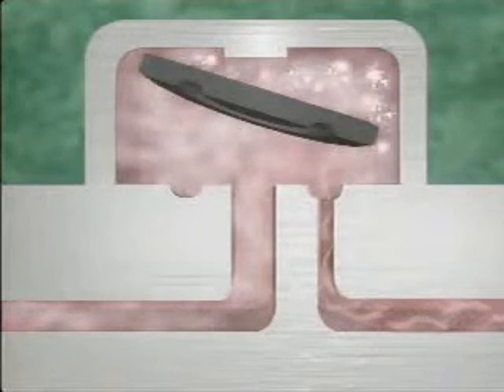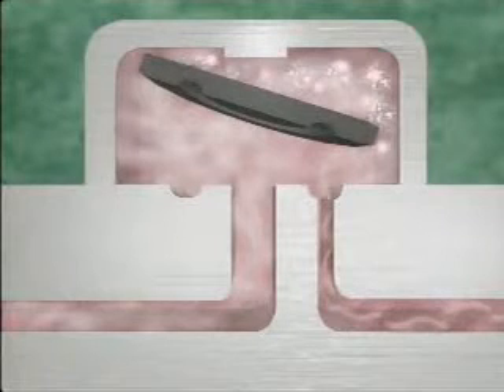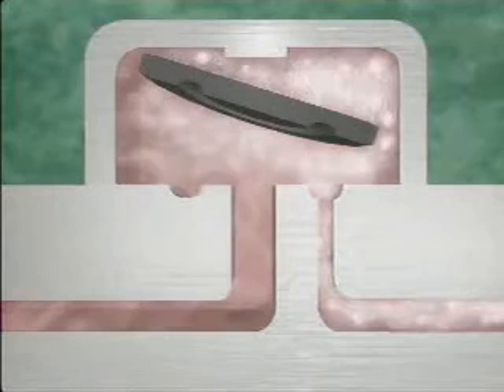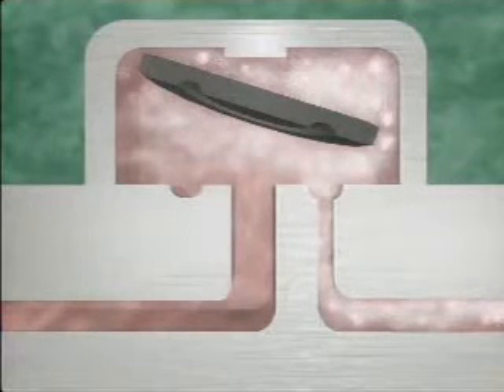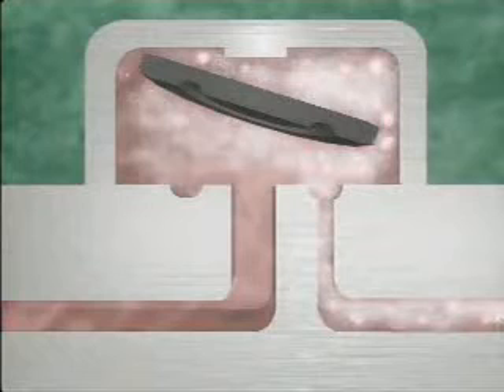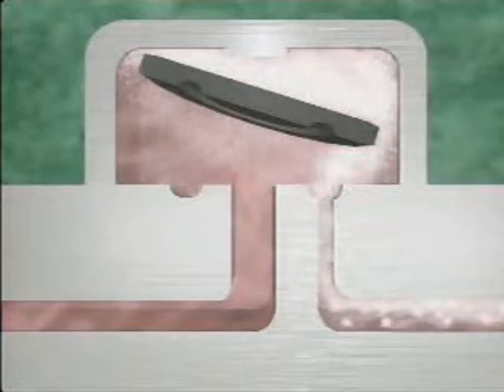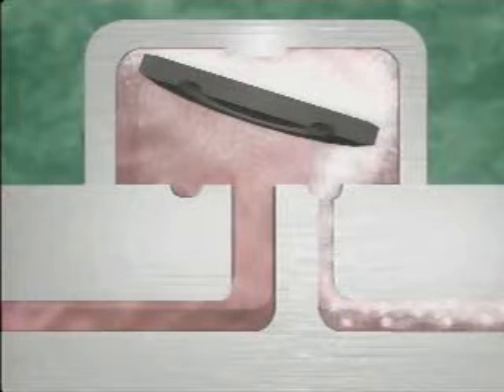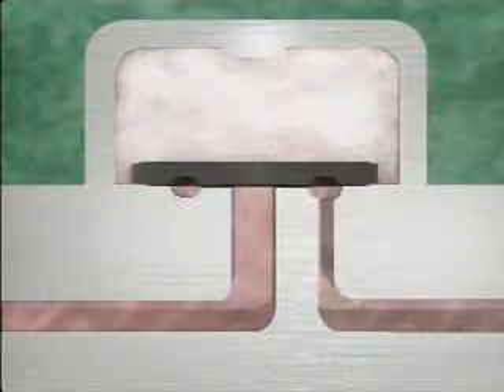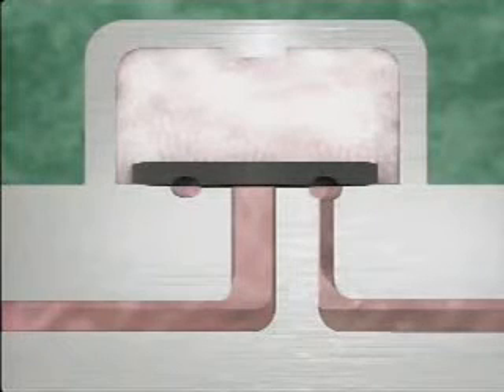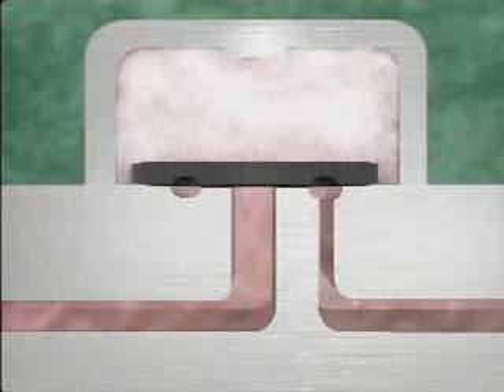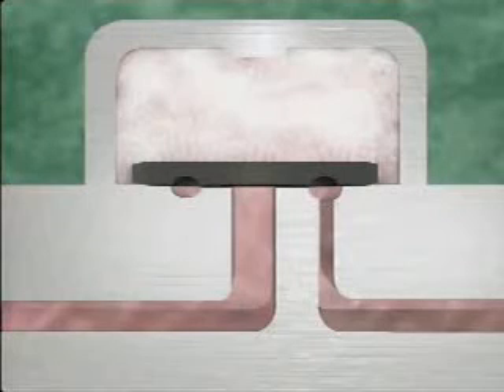This further increase in velocity reduces pressure on the underside of the disc. At the same time, flashing condensate flows out and causes a pressure buildup in the area above the disc. When sufficient pressure builds up here, while pressure on the underside of the disc has been reduced, the disc is forced down onto the seating surfaces, which closes the trap. The disc is held closed by the pressure of the steam that's in the chamber above the disc.